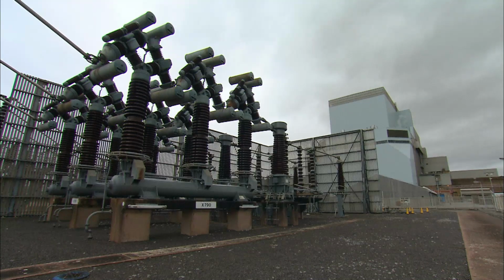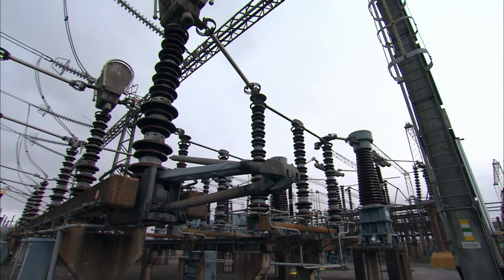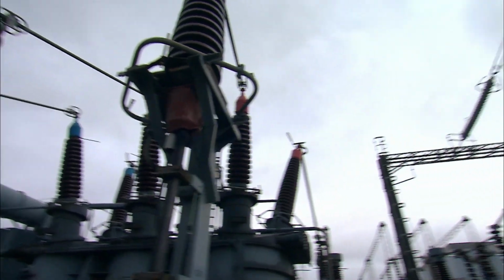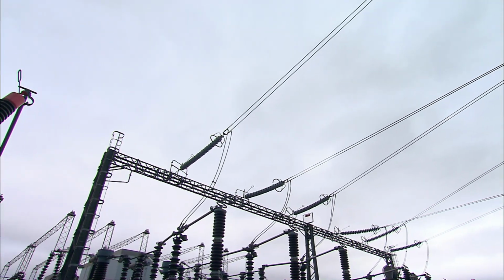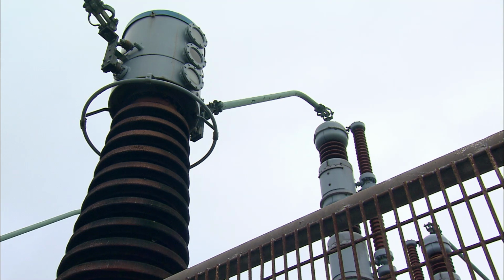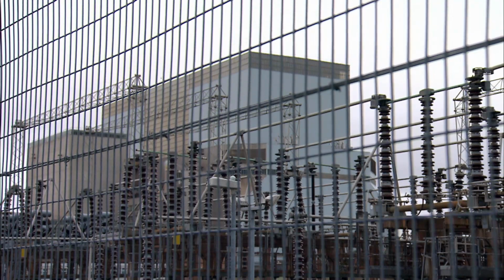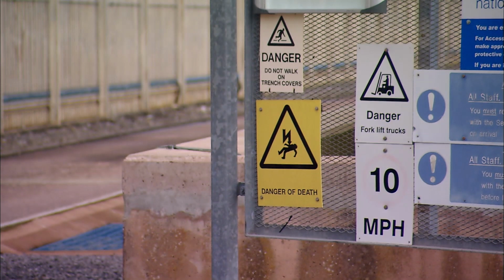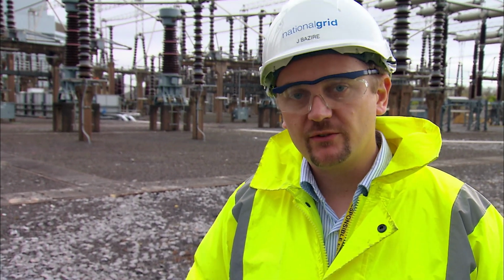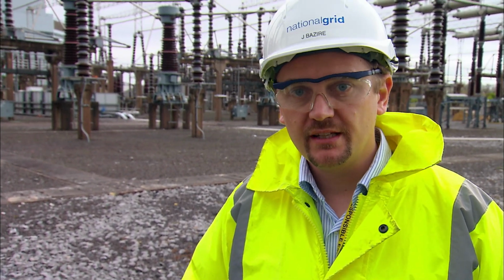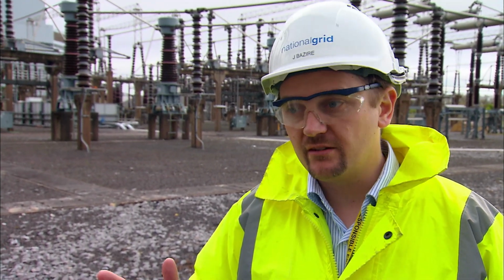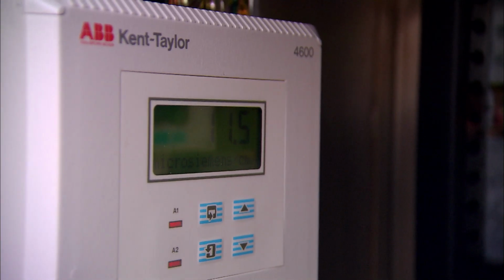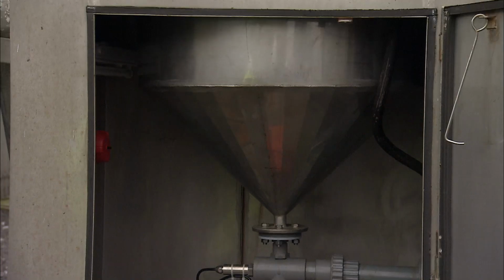But now they must turn to the 400,000 volt substation. The higher voltage means it's even more likely to flash over, when electricity flashes to the earth like a mini lightning bolt. But the extremely high voltage would make a manual wash far too dangerous. We can't manually wash here, it's just not safe to do so. We've got an automatic water wash system that runs totally independently, requires no manual input, and it can operate any time. And it makes a decision when it needs to wash.